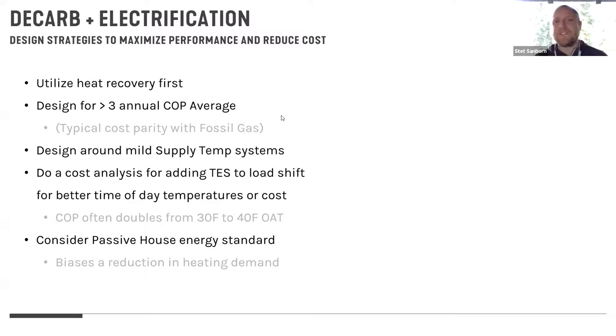And so the difference between our incoming air temp and what we're leaving the building isn't great enough for a runaround loop to provide more than 4 months of benefit. The rest of the year, that pumping energy might actually outweigh the energy recovery. For you guys, it's probably actually a lot better. But definitely think about using, especially the colder it is, a heat pump as your heat recovery mechanism. So active heat recovery in lieu of just a passive heat recovery through runaround loops.